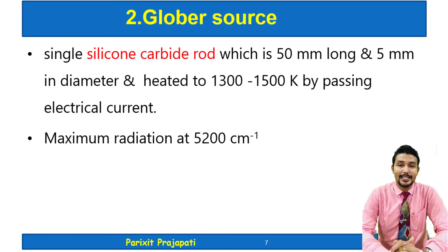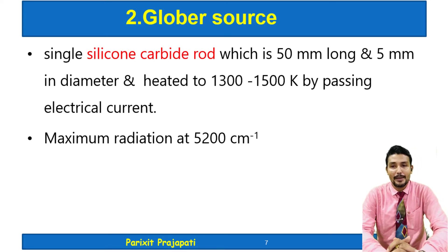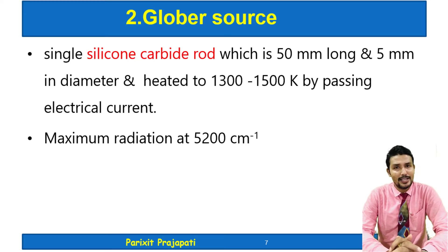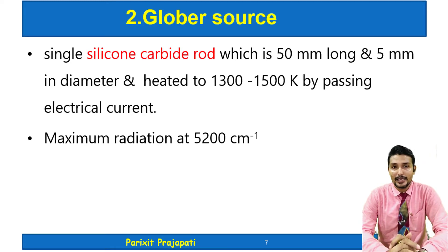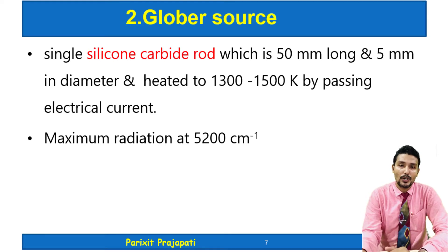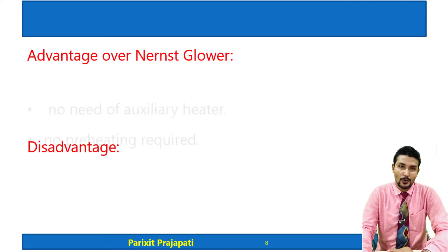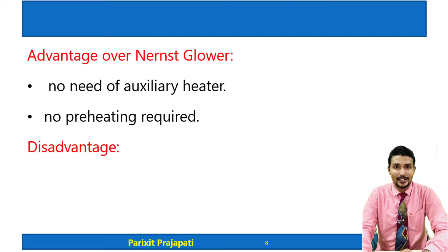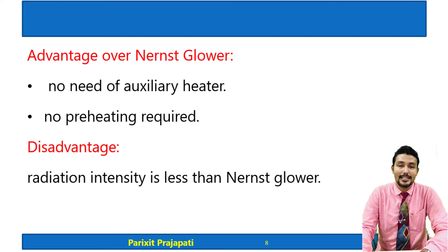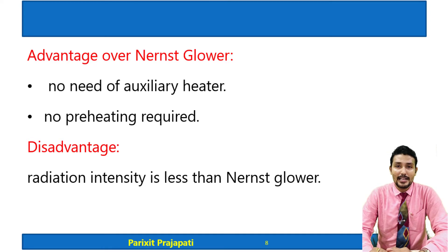The Globar source is a single silicon carbide rod having a length of 50 mm and diameter of 5 mm. It is heated at 1300 to 1500 Kelvin by passing electric current and produces maximum radiation around 5200 reciprocal centimeters. The advantage over the Nernst Glower is that an auxiliary heater is not needed as pre-heating is not required. The disadvantage is that radiation intensity is less than the Nernst Glower.